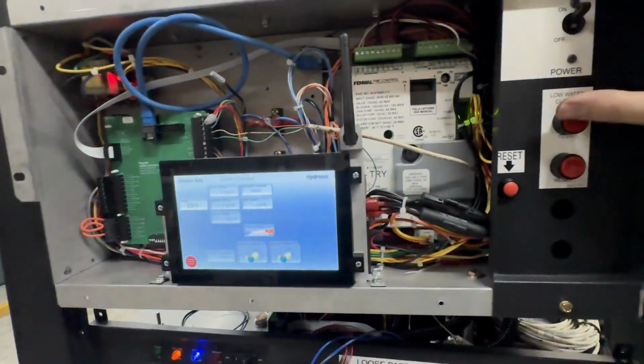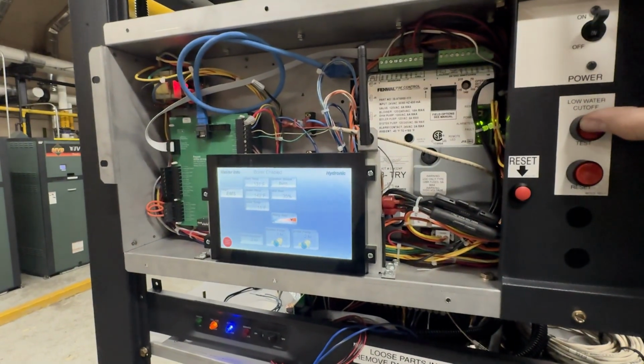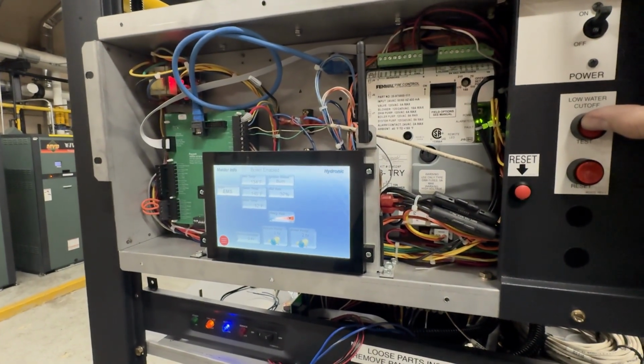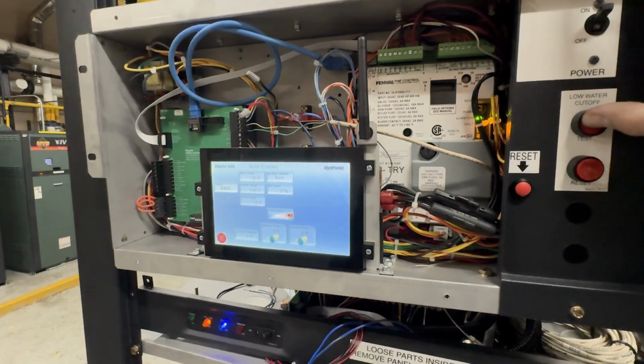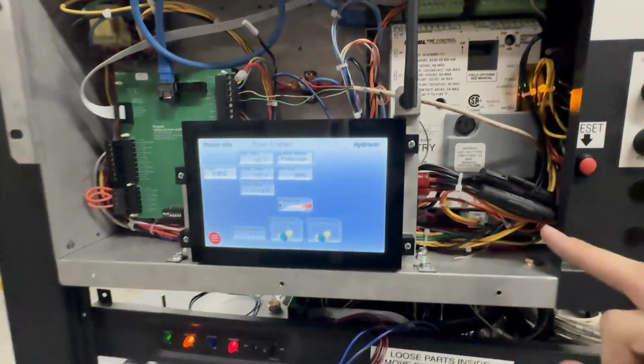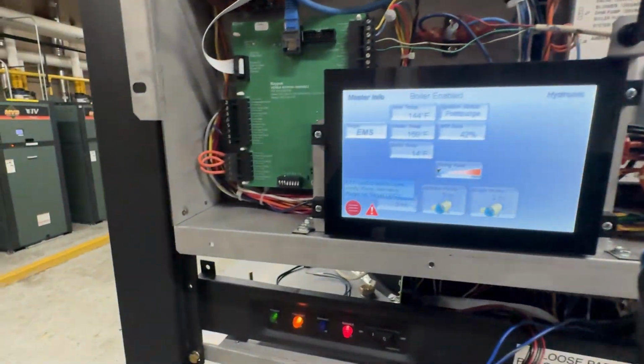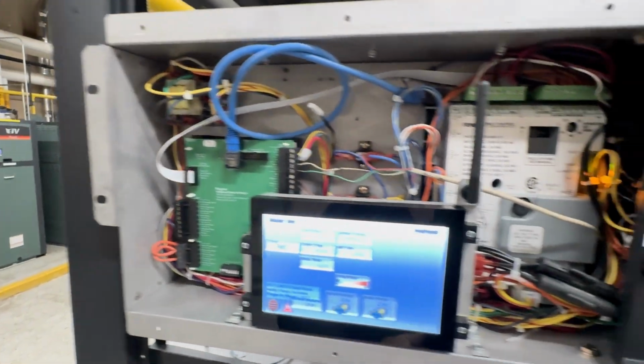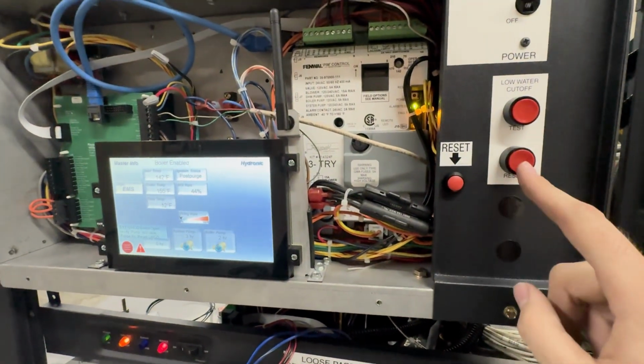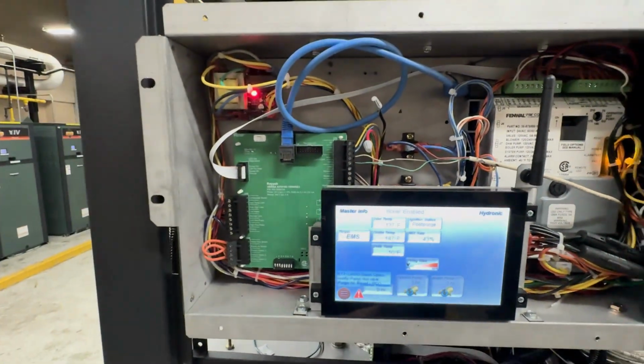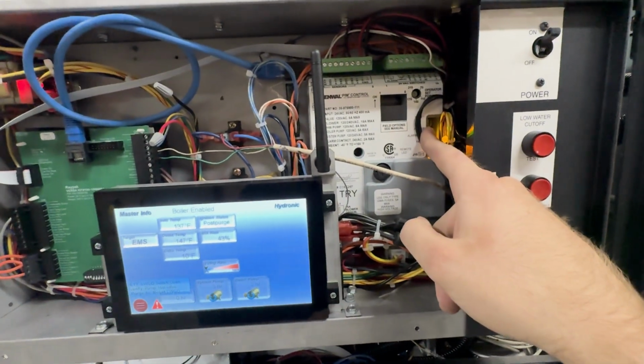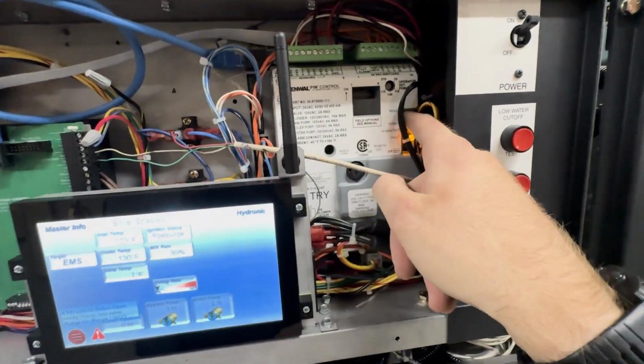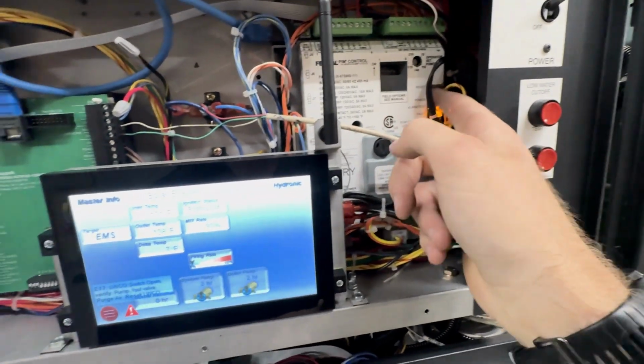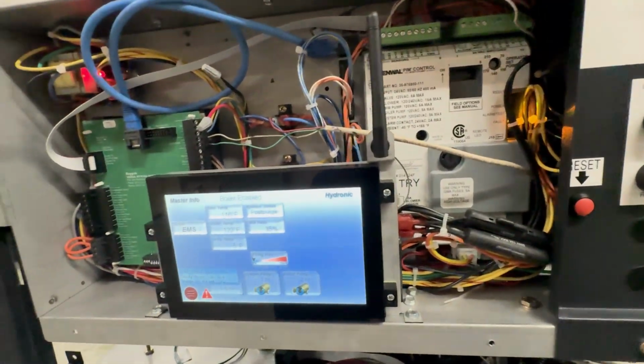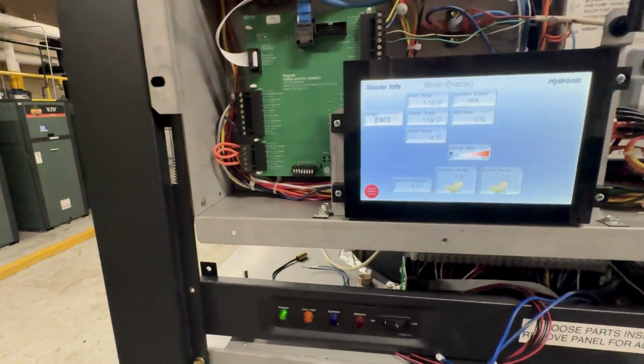This LED light right here should shut off, and that's going to trip the boiler. There's the light, and there the boiler tripped. You see we're popping an error code here. Service required. That LED is still off. The way we reset it, go ahead and hold the reset button right here. The light should turn back on. You may still have a code on your Fenwal control here. There's a reset button up top. Click the reset button, that code should be cleared. And then our service required light has gone off as well.